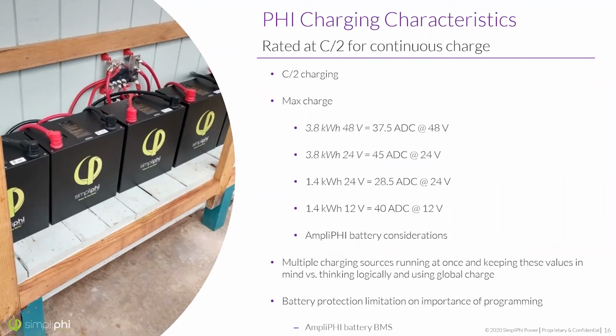So this value becomes a little bit less important for you to know. It is important to know if it's going to limit your PV output, but just know that the battery actually tells the charger at that point what to max charge. It's important to keep in mind this max charge rate when you have multiple charging sources running at once. There is something called global charge.